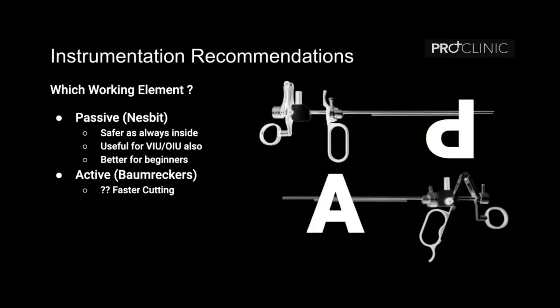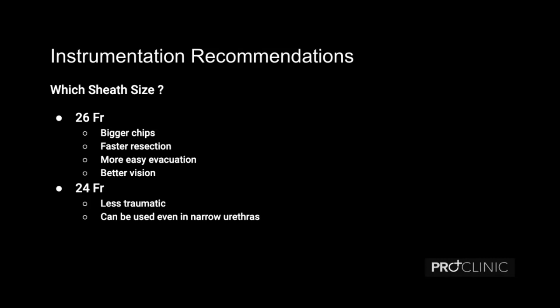In the passive working element, you deploy the loop and the cutting happens passively by the spring action — you just leave it and slowly it comes back cutting the tissue. In the active type, you use your fingers to actively cut the prostatic tissue. Which sheath size is recommended? It's a personal opinion, but less traumatic things are better; the problem is that smaller sheaths give smaller chips and slower resection. Many people prefer the 26 French standard outer sheath — there are bigger chips, faster resection, easier evacuation, and better vision.